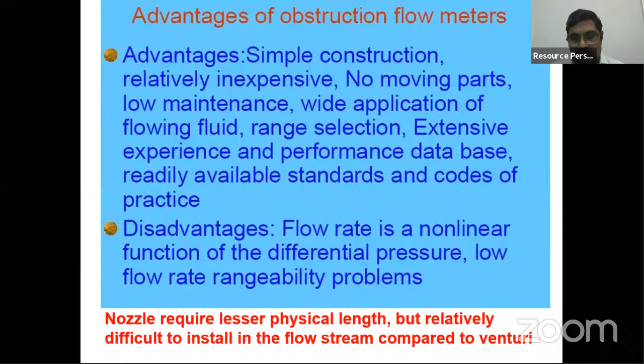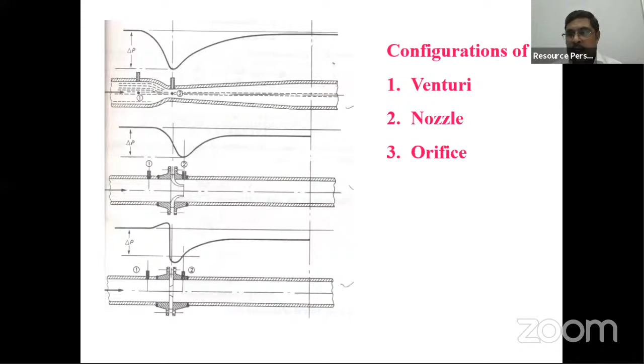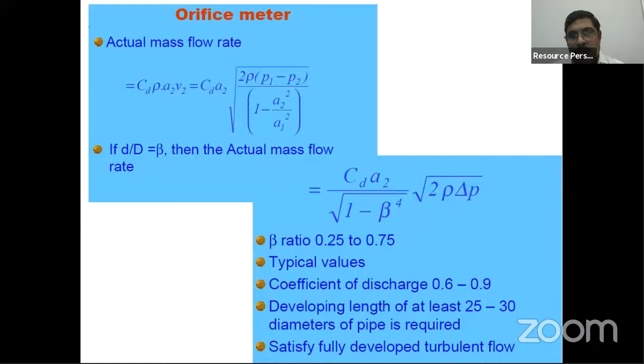Whenever you make the tapping, particularly when you use the nozzle, this is the nozzle, this is the orifice. You have to make a tapping, one on the upstream side, maybe 1 inch from the nozzle, and on the downstream side it should be ½ inch. The ratio should be 1 to 1.5 inch. Basically, on the downstream side the vena contracta will develop exactly ½ inch from this one. So one tapping should be taken at the normal pipe, and another close to the vena contracta, so that between these two sections you have the maximum pressure drop. Whenever you make the pressure tapping, you must remember this.